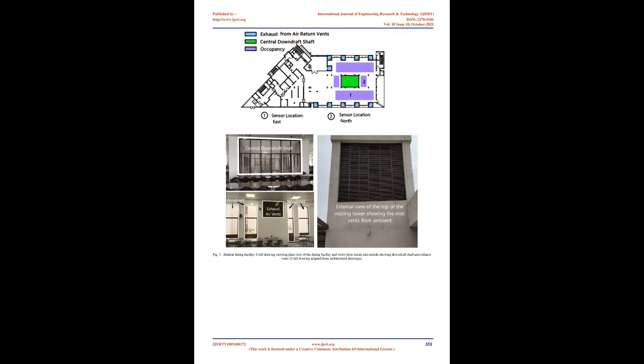The manufacturers and maintenance crew of the electronic equipment in the classrooms also frequently complained about very high humidity, condensation, and wetness in the classrooms, accompanied by warnings of danger to the equipment if the high humidity persisted for extended periods of time. While the humidity levels can be controlled by adjusting the misting pump pressure, frequent fluctuations in ambient relative humidity meant that the misting pressure had to be readjusted sometimes on a daily basis. A spike in ambient relative humidity that was not met with a corresponding lowering of misting pressure would cause very high relative humidity levels within the classrooms, with condensation on various surfaces and sometimes even water logging in some parts of the classroom. Such situations were frequently encountered, especially in June with the approach of monsoon.